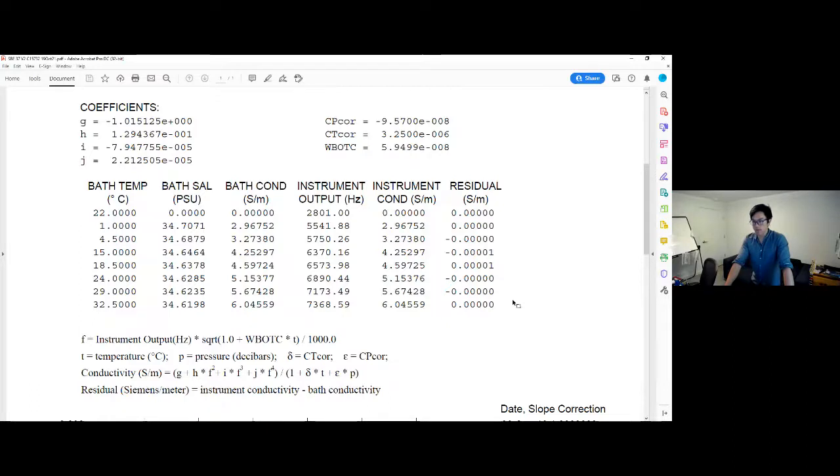That fresh water does have some conductivity. And then it's going to be higher than 2801. And then your pump is going to say, okay, we've met the minimum conductivity frequency threshold for pump to turn on. And then it's going to be able to turn on once you start logging some data.